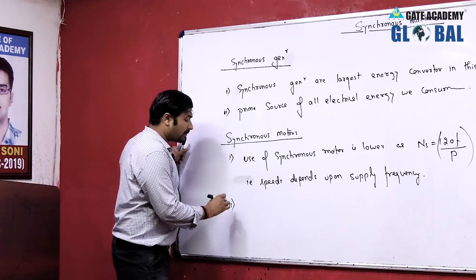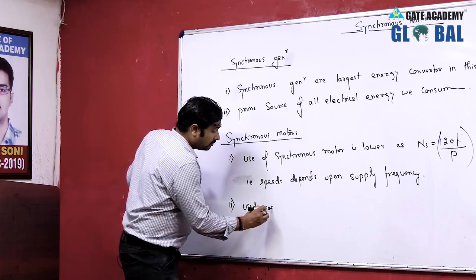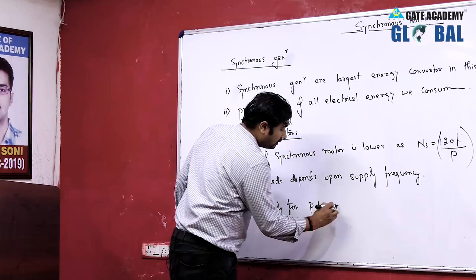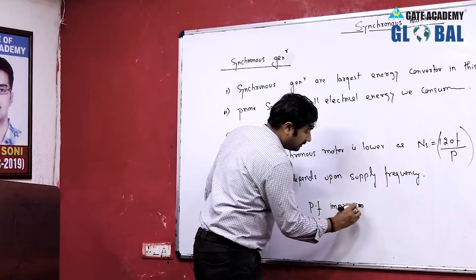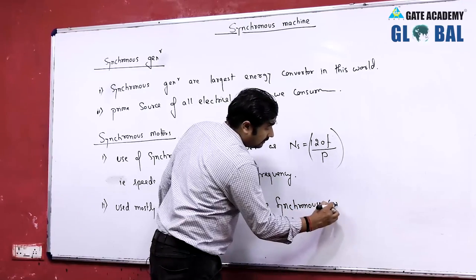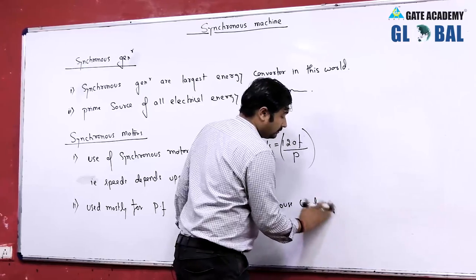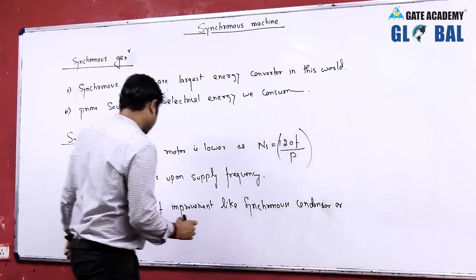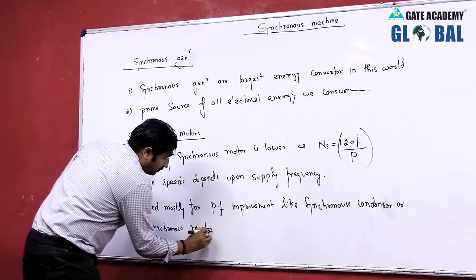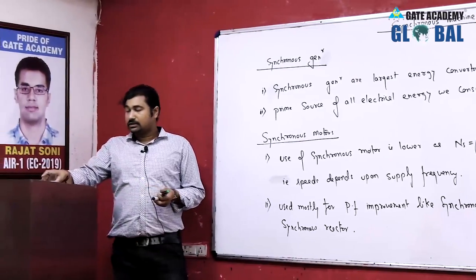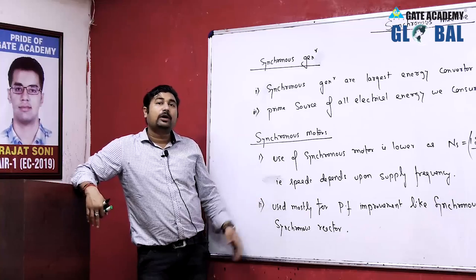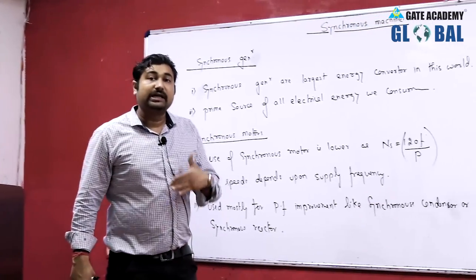Synchronous motors are generally used for power factor improvement — mostly used as synchronous condensers or synchronous reactors, also called rotating VAR compensators. The speed of the synchronous motor mainly depends on frequency. Three-phase synchronous motor is not a self-starting motor, so there will be a problem of desynchronization if the supply frequency to the motor changes.